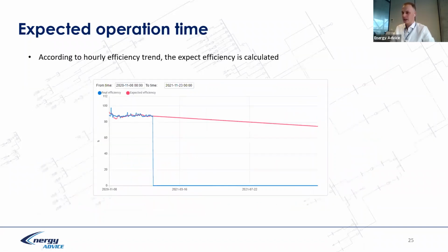Expected operation time. When we monitor the efficiency of a boiler every 5 minutes, we understand the influence of the water content or calorific value of the fuel on the efficiency. We understand the efficiency dependence on the loading of a boiler. For example, lower efficiency at higher heat demand, and higher efficiency at lower demand. Knowing this data, we can forecast a decrease of efficiency. So when we can forecast the decrease, you can understand that somewhere here it won't be an acceptable level of efficiency, and you should do maintenance activities.